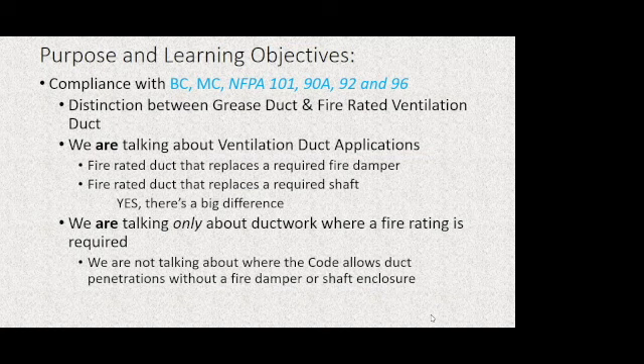The reason for this is that grease duct is tested to different standards, and they are largely followed well within the wild, as I like to put it. That is in contrast to the fire-rated ventilation ducts for most other applications where we find code paths to fire resistance, because the test standards are different and the implementation is different. And we're going to find that that's where much of the confusion comes from, because the fire-rated ventilation duct designs that are supposed to be used were either born here in the US market from the grease duct industry, or they were born over in the UK or British industries, where their code systems are very different, and those differences matter.